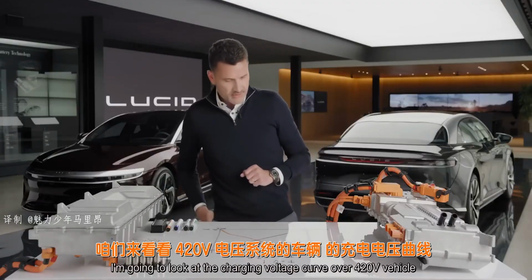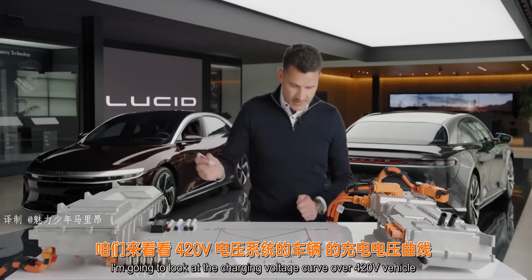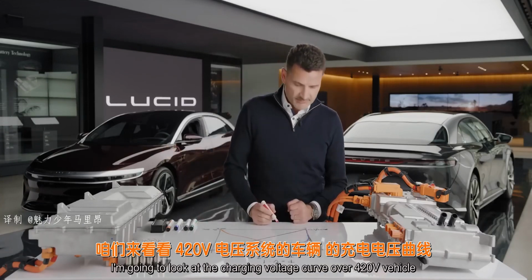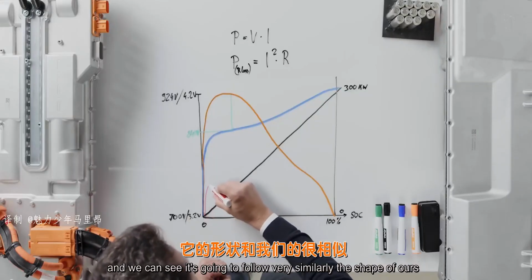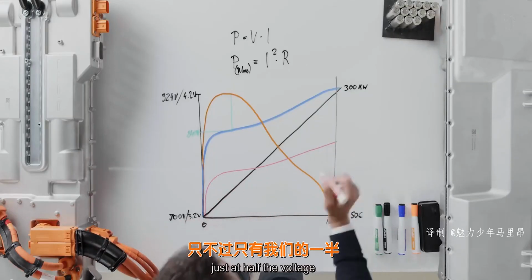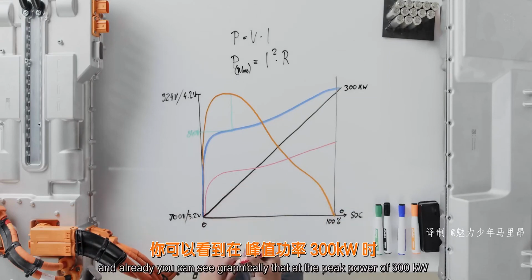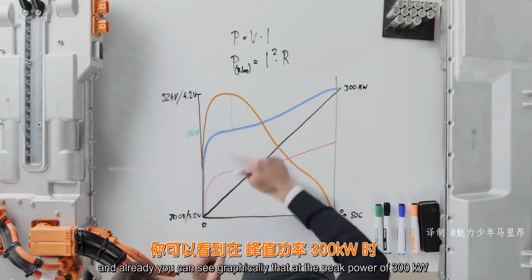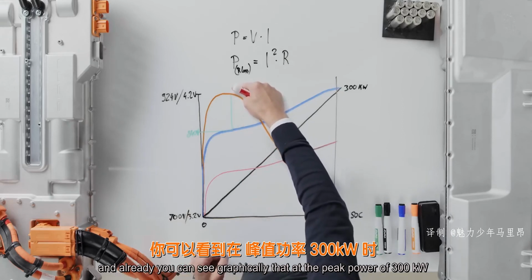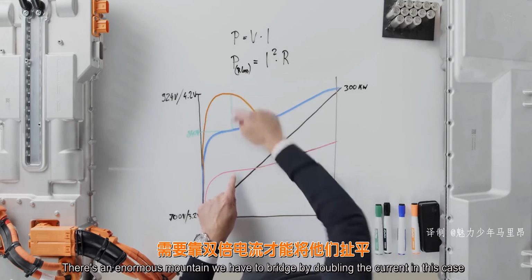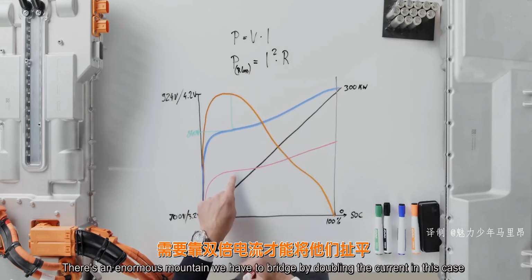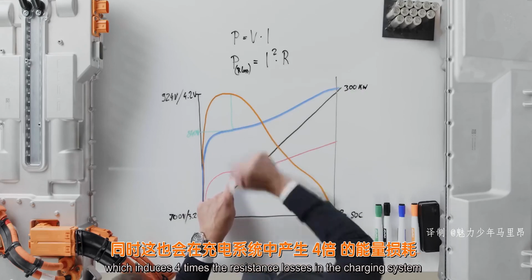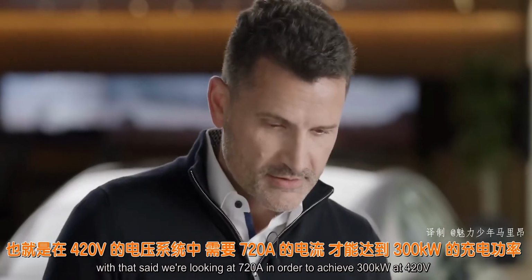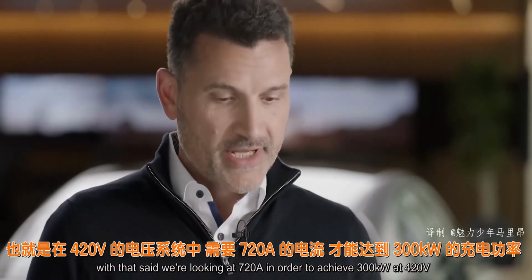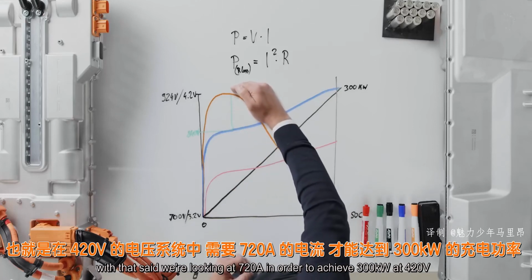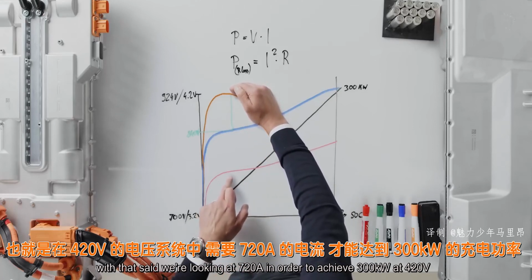Now let's look at the charging voltage curve of a 420 volt vehicle. It follows a very similar shape to ours, just at half the voltage. Graphically, at the peak power of 300 kilowatts, there's an enormous mountain to bridge by doubling the current, which induces 4 times the resistance losses in the charging system. We're looking at about 720 amperes in order to achieve 300 kilowatts at 420 volts.